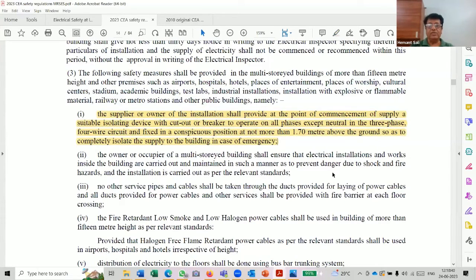If you see IEC 60364 part 5-56, they have given a sample diagram of this. They call it a fire switch. According to that, if you see, they have bypassed all emergency services before placing this switch in the circuit. So correction is very much needed, because while the evacuation process is going on, emergency services must keep running, and with the switch in the off position, that cannot be done. All emergency lighting, all your security services, door openings, or smoke extraction systems, everything will fail. Escape route lighting, etc. So I think there should be a connection for these emergency services.